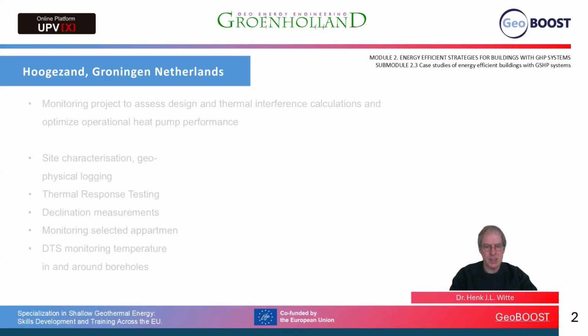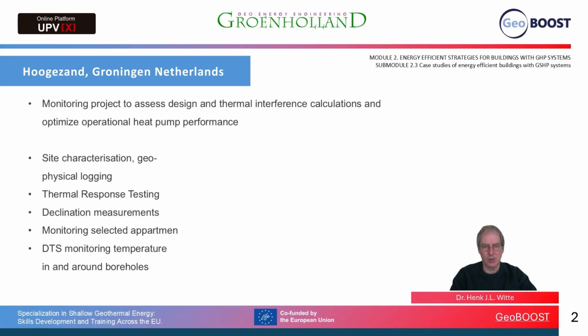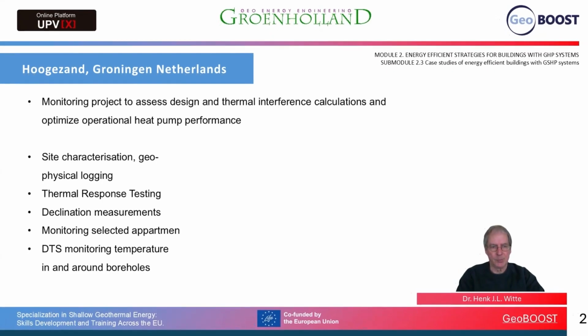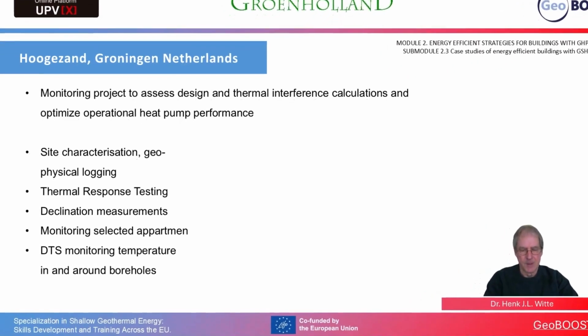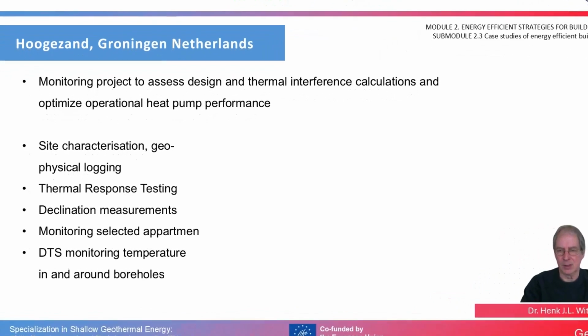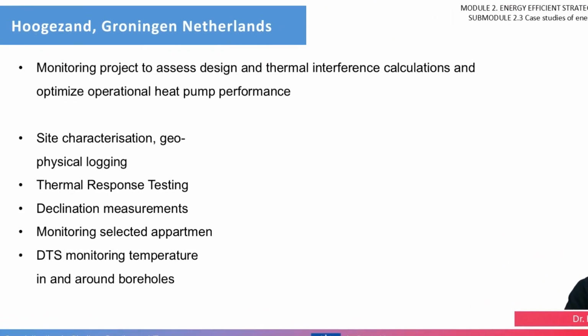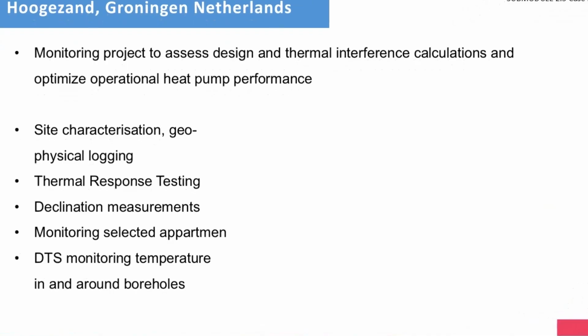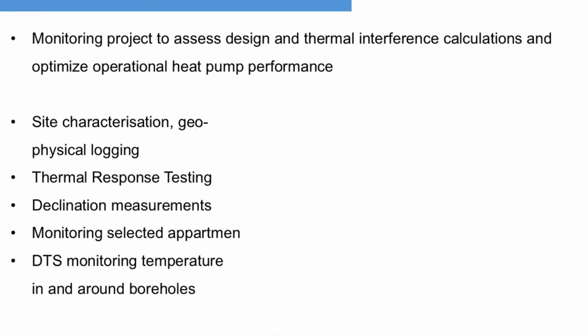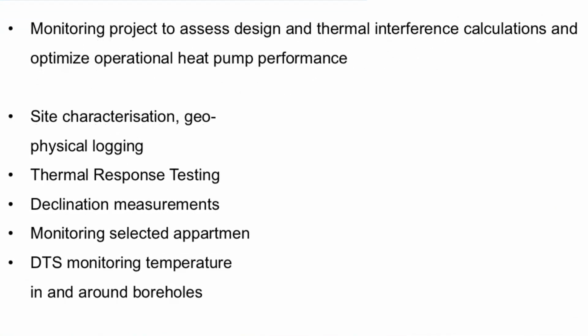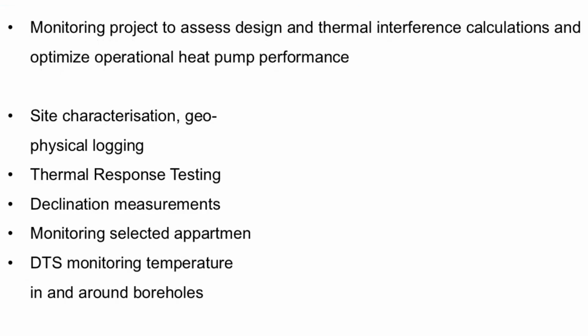The project itself is a monitoring project to assess design and thermal interference calculations and optimize operational heat pump performance. Different steps were taken. First of all, we had a very detailed site characterization, including geophysical logging of boreholes and thermal response testing of 3 boreholes. We even had declination measurements, so measuring how vertical the boreholes are drilled.